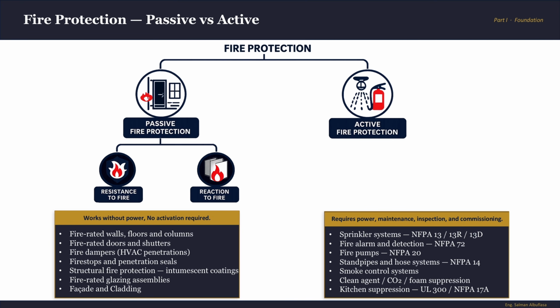And if fire broke out in one wing, the walls contain it. Nobody activates anything, nothing needs power. This is what's meant by passive fire protection. It's built into the structure itself. Picture a wall holding back an invading army with no ammunition used, no power needed, and no one giving orders. It's just there doing its job. This is the passive fire protection. And an example of passive fire protection are fire-rated walls, fire-rated doors, dampers, and fire stoppers.